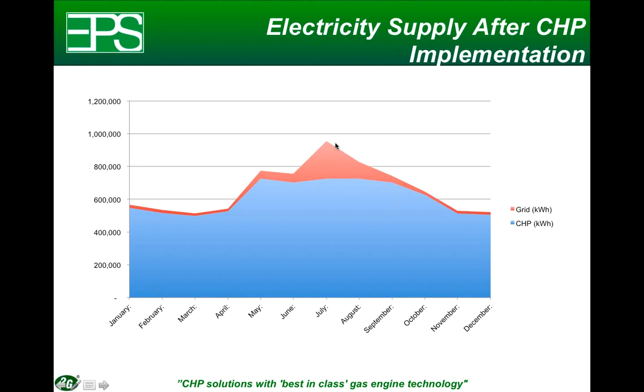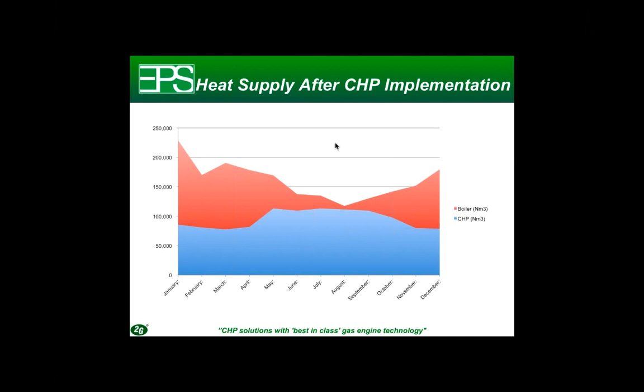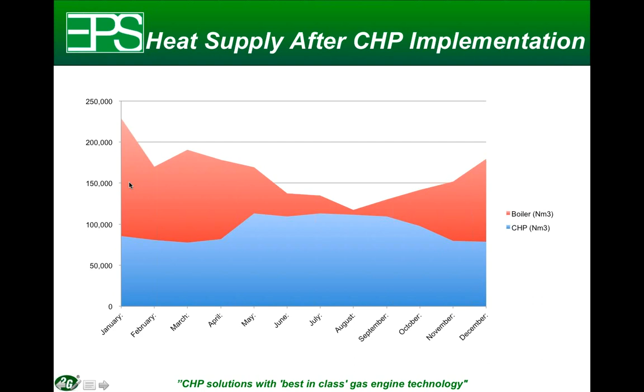If they proceed with a cogeneration system, you can see what happens. Most of their energy now comes from CHP. In electricity, you see that most of the electricity now comes from the CHP unit, and a little bit comes from the grid. If you look at what happens with the heat supply, most of the heat supplied throughout the year now comes from the CHP unit, and the remainder is supplemented by the boiler system.